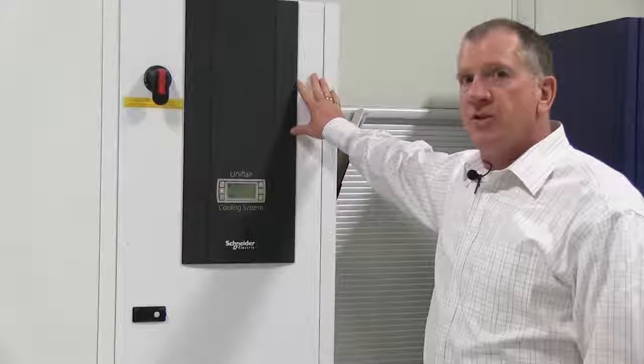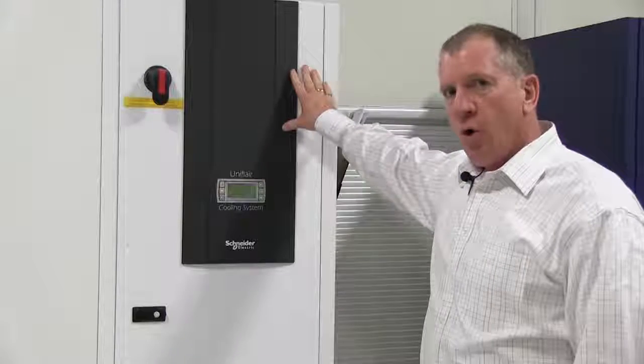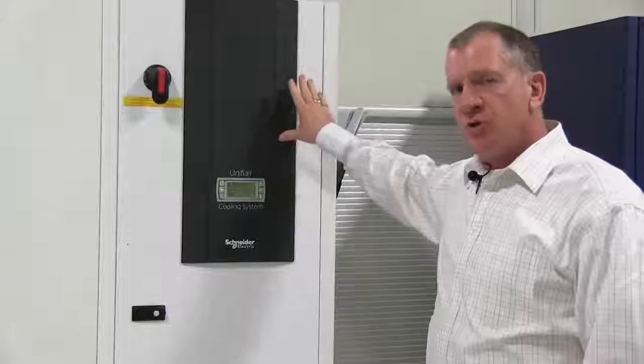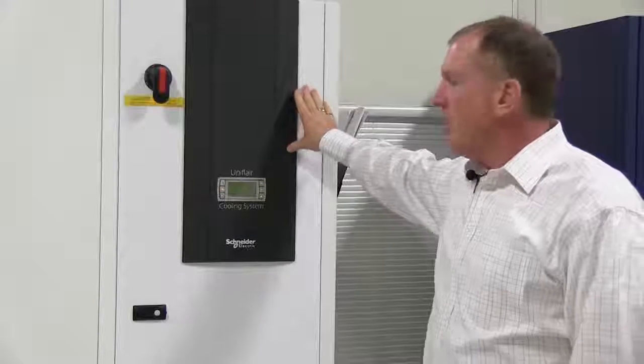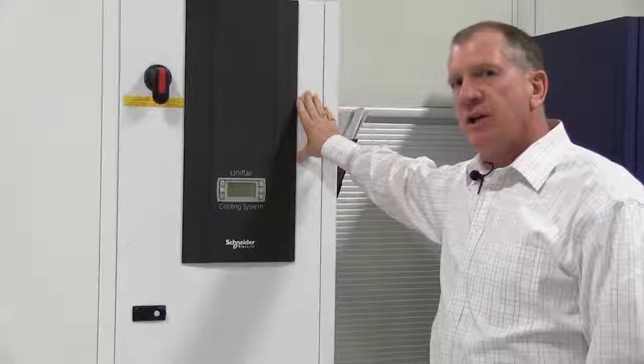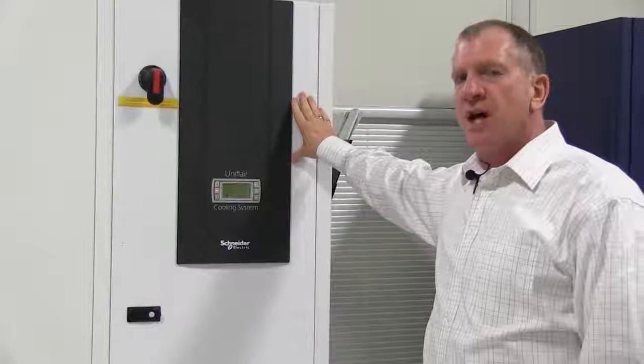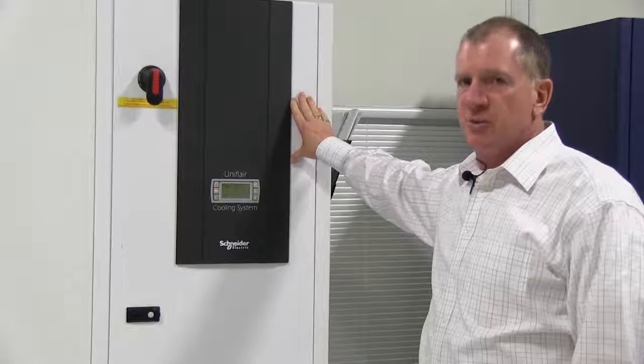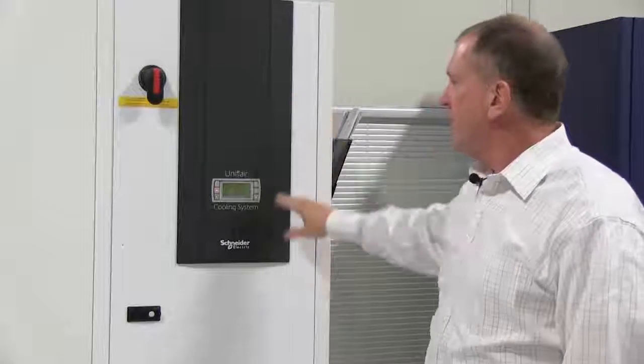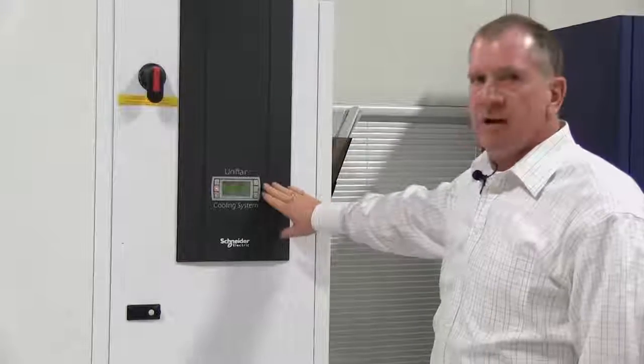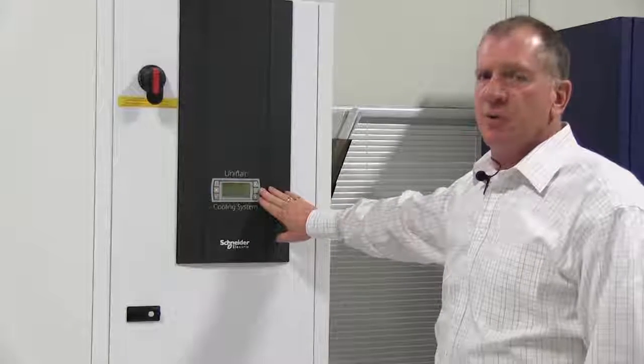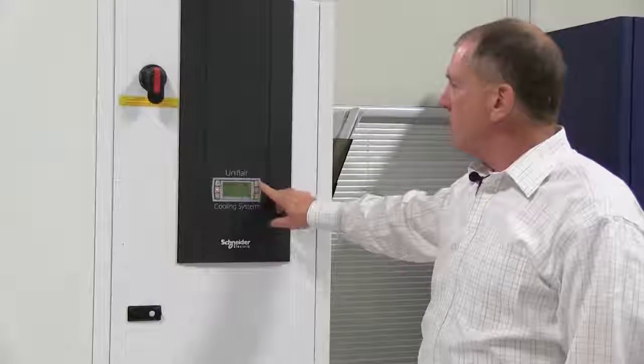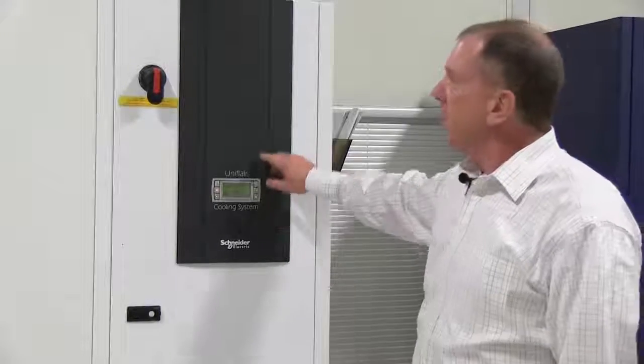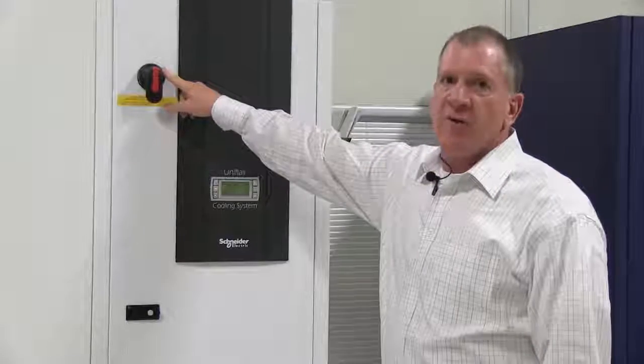All the Uniflair units have external double wall insulated panels to reduce sound power levels in the room. All the units carry a weighted sound level for the room of 62 decibels or less. On the front panel, we also have the LCD backlit operator display with both numeric and graphical icons and a lockable non-fuse disconnect switch.